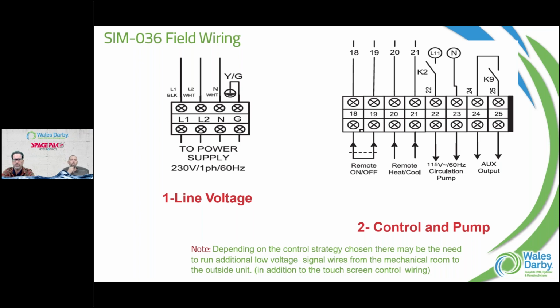So field wiring for you guys out there, you've got your line voltage coming in, so you have 230 volts. And then as far as controlling the system, we need a feed. These are dry contacts. They're going to be a 2-wire to the remote on-off terminals, and then the heat/cool. So we want to know when that outdoor unit needs to come on, and we want to know what mode I need to be in, heating or cool, right? So those are the 2 connections we do have. You'll notice, even on the power supply side, when we are saying we want 230 volts, that's 2 legs and a ground. We also want a neutral sent out there as well, as you can see here, if I highlight that in the middle there. We want the neutral coming out, so a 4-wire, that's got to be communicated to your electrician.